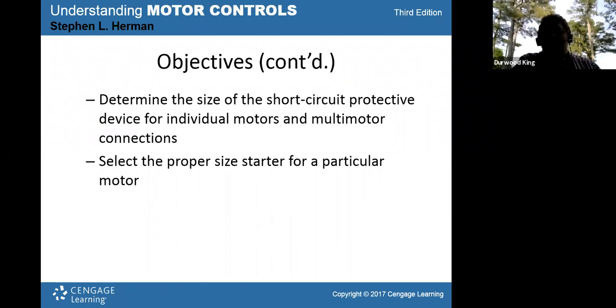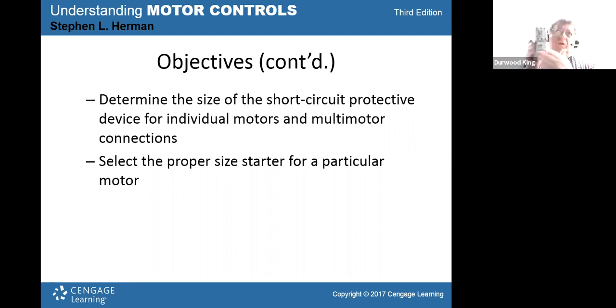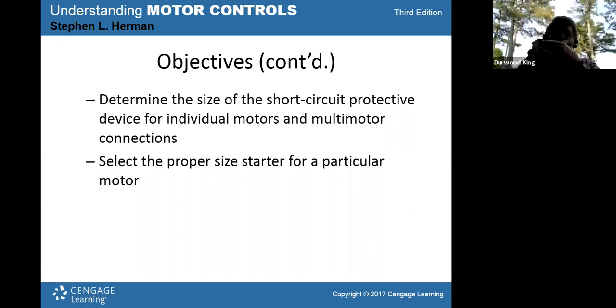We'll look at how you size your short circuit protection devices that actually go ahead of the starter. With your starter, you have the overload relay under it that's going to protect the motor. And then above it, you're going to have either fuses or circuit breakers that feed the starter. That's what they call your short circuit protective device. That's something upstream from that starter. And we're going to look at that.